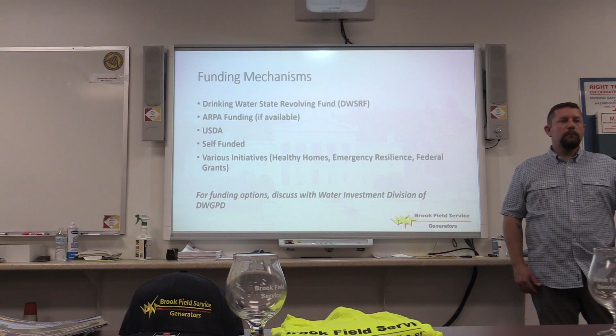Jim, does your company offer services to come and do a facility analysis for load studies on the gear, everything like that? Yep, we have equipment that we put in, typically for a week or two, and we do a power study. We see all your power peaks and amps, and if there are any unusual spikes, so that we know what type of generator to look at through that analysis. Again, we don't charge for that. We'll set it for a couple of weeks for you, and then we can give you an estimate so that when you're applying for your grant, you don't underfund yourself.